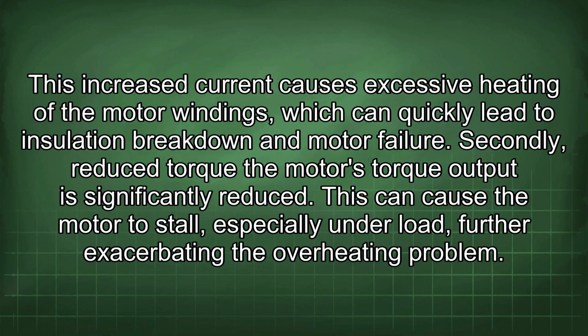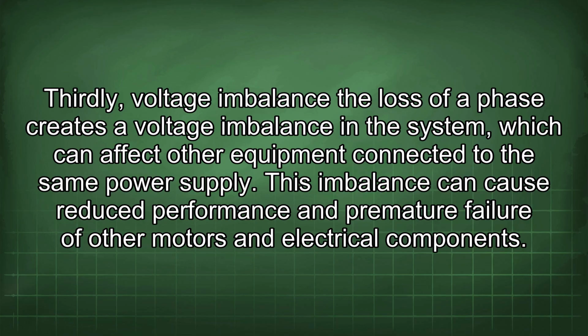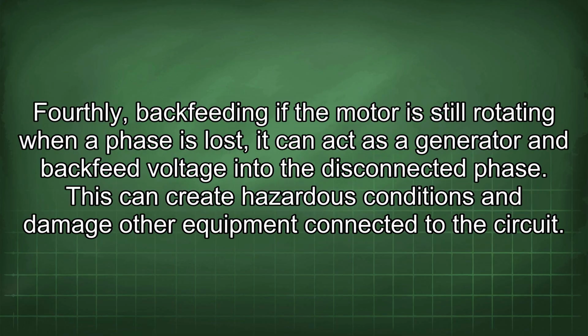Secondly, reduced torque. The motor's torque output is significantly reduced. This can cause the motor to stall, especially under load, further exacerbating the overheating problem. Thirdly, voltage imbalance. The loss of a phase creates a voltage imbalance in the system, which can affect other equipment connected to the same power supply. This imbalance can cause reduced performance and premature failure of other motors and electrical components. Fourthly, backfeeding. If the motor is still rotating when a phase is lost, it can act as a generator and backfeed voltage into the disconnected phase.